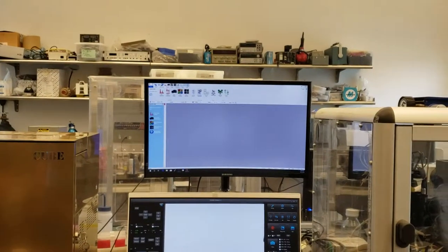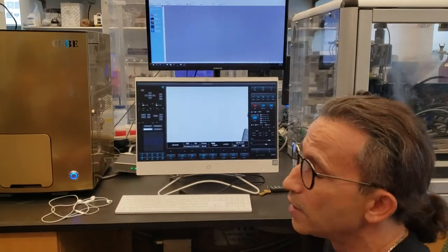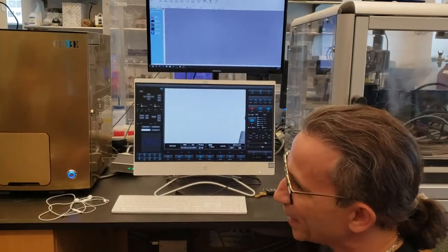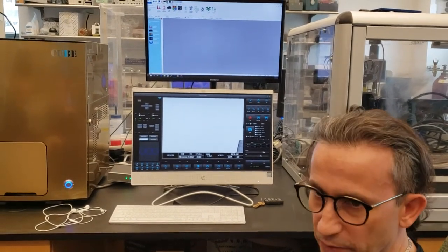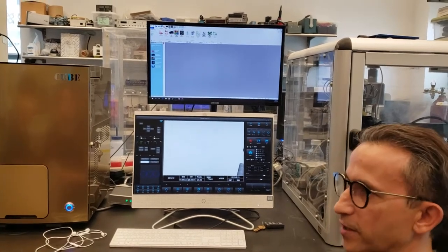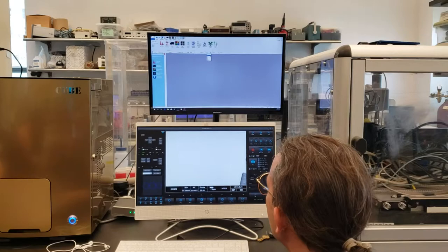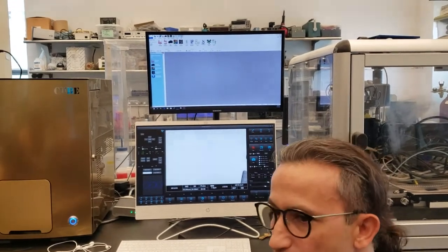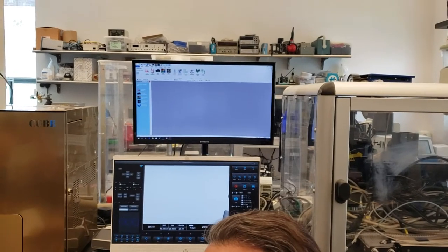For your normal everyday bulk analysis and bulk work, you can work at time constant 4. Even at time constant 2, that's a really good resolution time constant as well. But if you work at 0.5 and 0.25, the spectral peak information might get a little bit more dense or wider. So for now, we're going to learn how to crawl, and I'm going to leave you guys at time constant 4. I just went through this whole explanation to let you know what this is on this bar. This is very, very important, and that's why I'm talking about it.